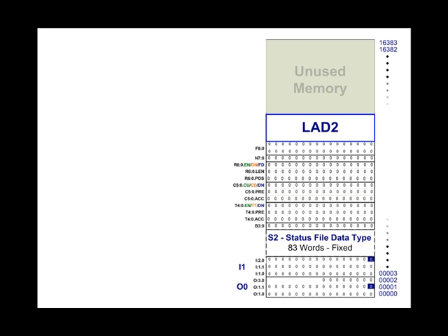Ladder 3 through ladder 255, however, require a special instruction to jump from ladder 2 to their location in memory and to execute them, because they are actually subroutines and they are subject to the execution of ladder 2. With data files and program files, the file numbers are arbitrary.